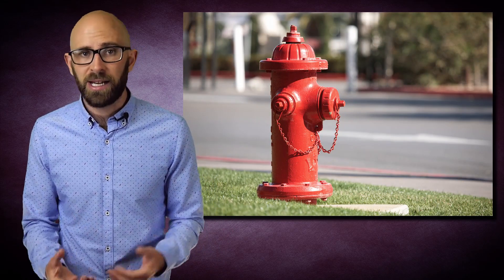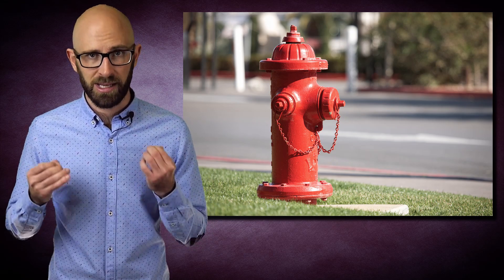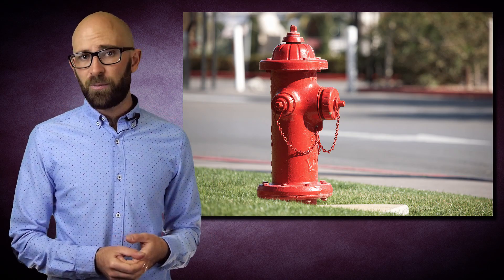If the fire hydrant is not hooked to the public water system but instead is accessing a private system — such as a shared well by several houses in a specific neighborhood — the hydrant should be painted a color distinguishing it from a publicly supplied system. In this case, the NFPA recommends the color red. OSHA, the Occupational Safety and Health Administration, further recommends that a hydrant be painted violet for any source that is non-potable, though this can cause confusion when a hydrant is both non-potable and from a private source. If a hydrant is inoperable, it should be painted black, or if only temporarily inoperable, a black bag is commonly placed over it.